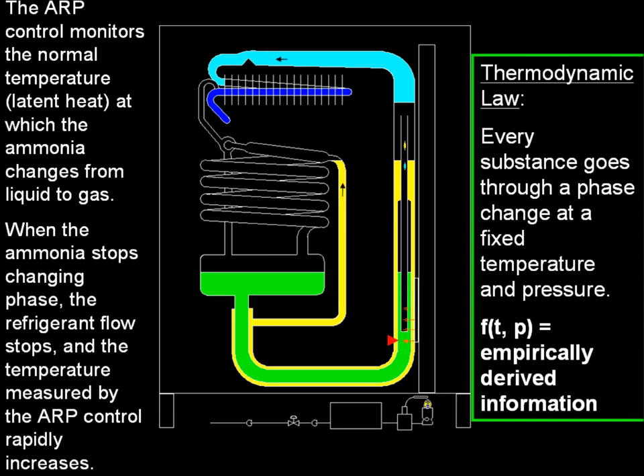The ARP control monitors the normal temperature — that is, the latent heat necessary to drive the cycle — at which the ammonia changes from liquid to gas. When the ammonia stops changing phase, the refrigerant flow stops and the temperature measured by the ARP control rapidly increases.